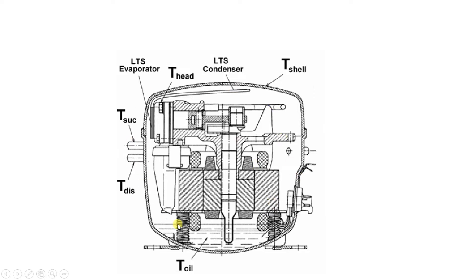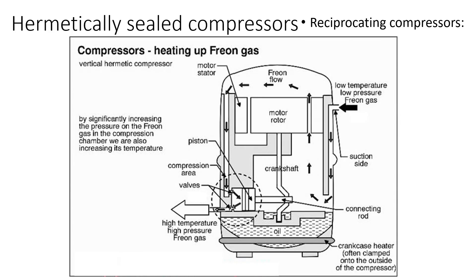This is the actual latest model of the hermetically sealed compressor. Advantages of hermetically sealed compressors: leakage of refrigerant is prevented because suction and discharge are all inside the welded shell, making it leak proof. Since both motor and compressor are inside the shell, noise is less. It requires small space due to compactness, and lubrication is simple.